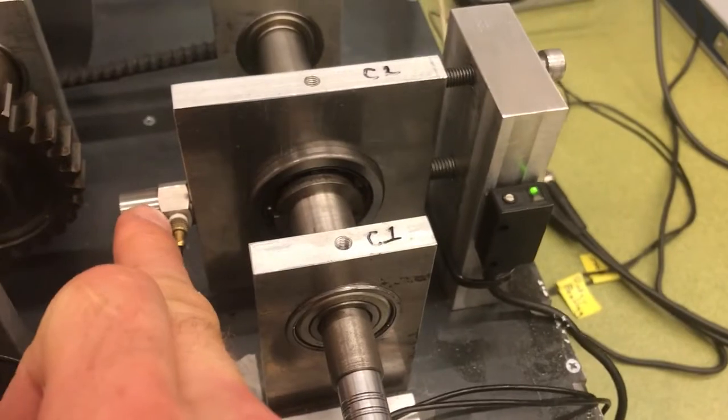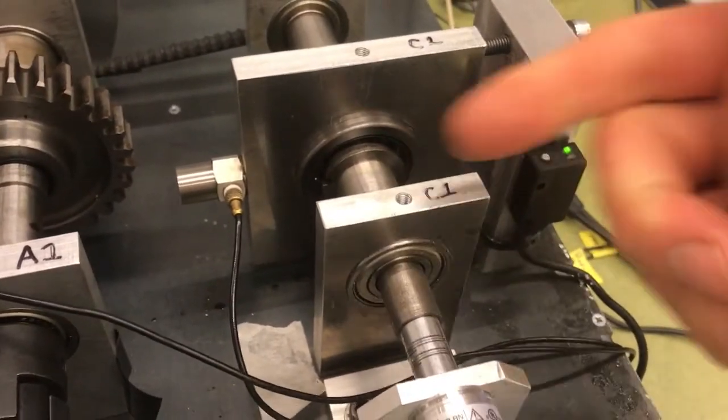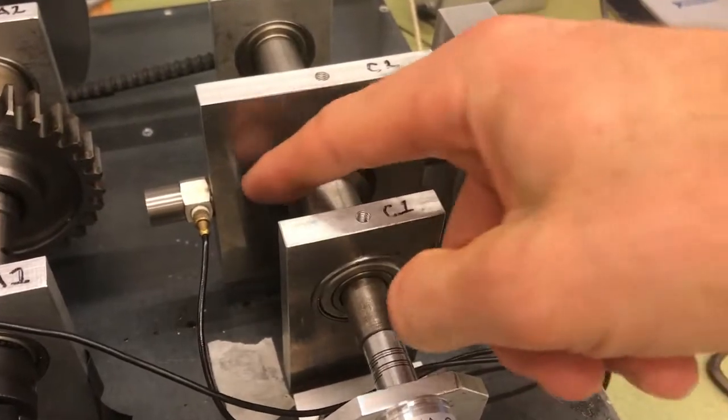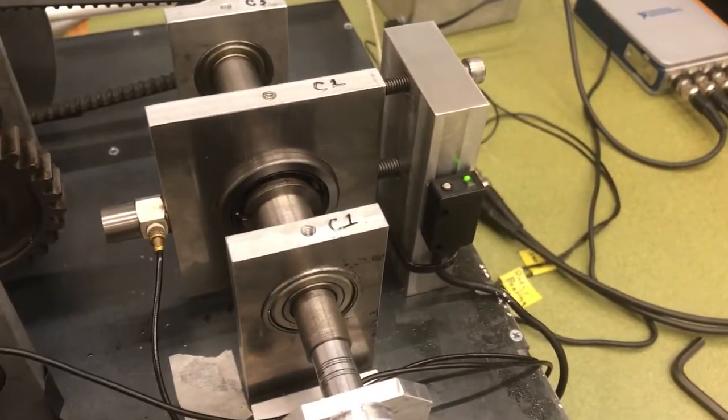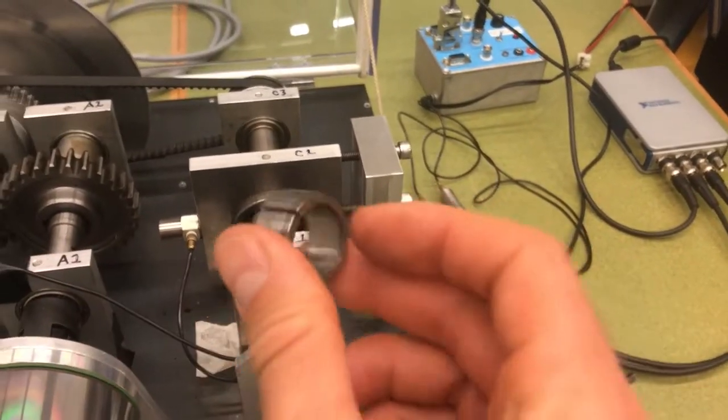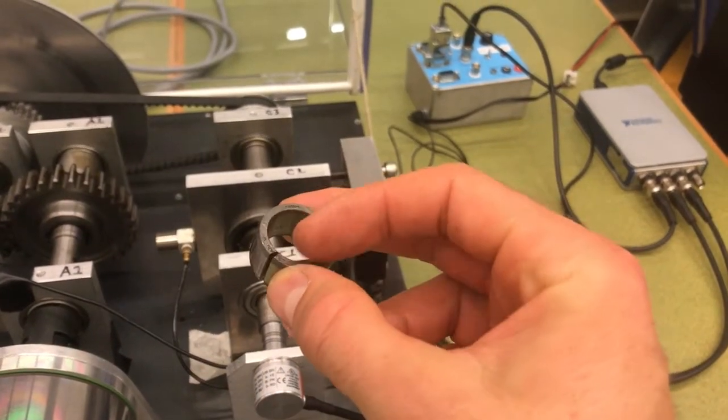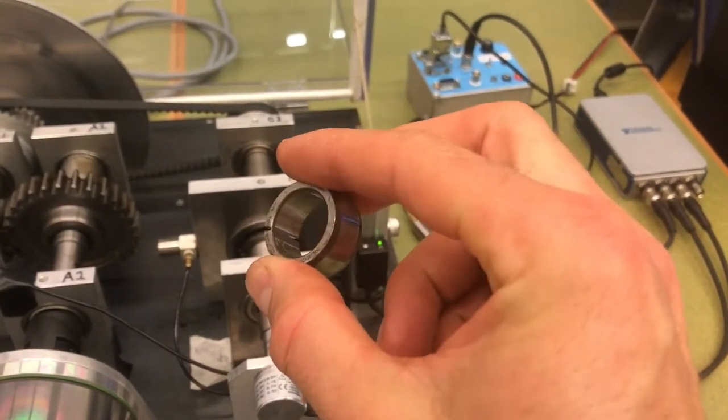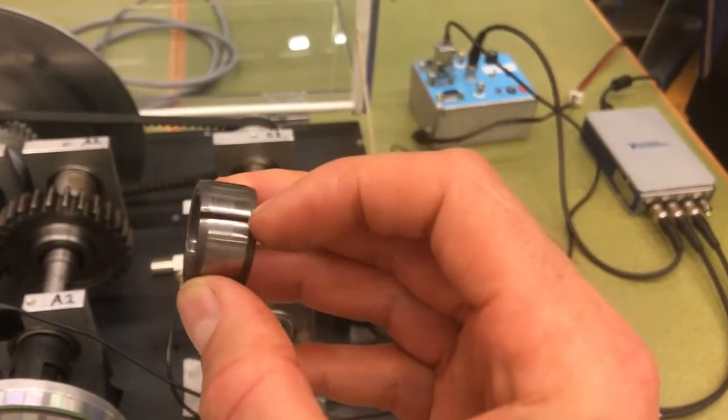Lastly I've got another accelerometer mounted over here which is clearly measuring the acceleration through this bearing here on this bearing block. Now this bearing has been deliberately damaged to be able to demonstrate the way that we can make vibration measurements of rotating systems to determine something about their nature.